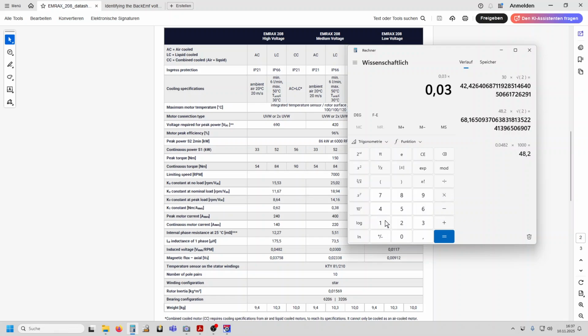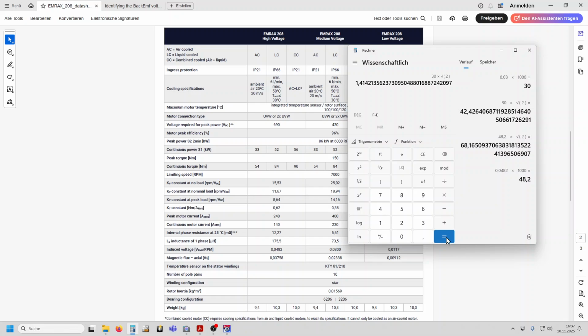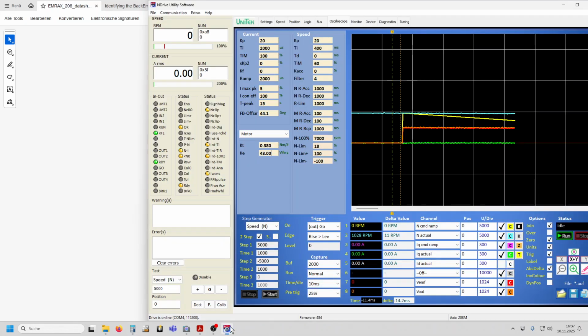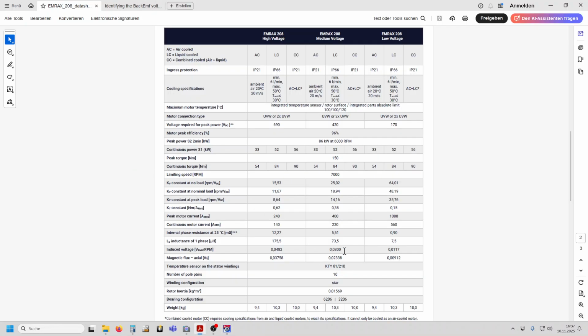And if we open our calculator, 0.03 multiplied by 1000 multiplied by the square root of 2, 42.42 volt per 1000 RPM, which is almost exactly what we have estimated using this process. And we have confirmed that it is a medium voltage motor and not a low voltage or a high voltage motor, which is great.